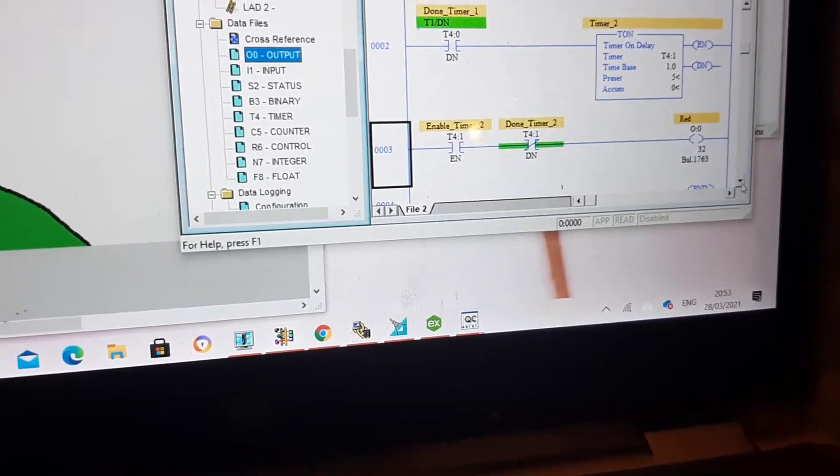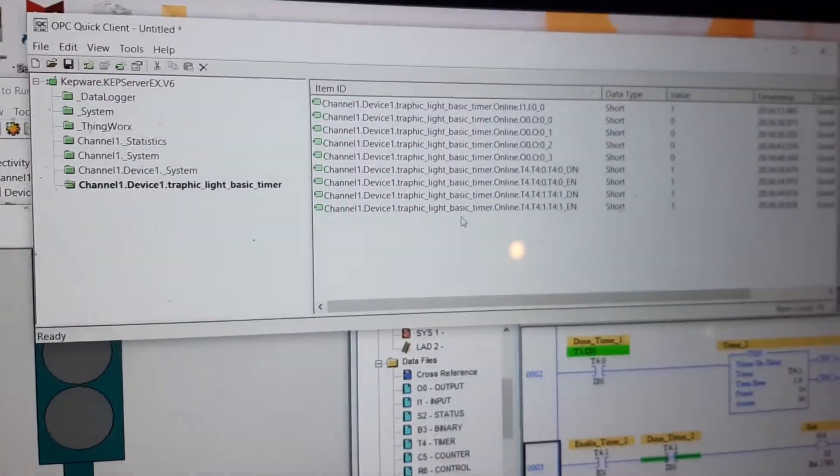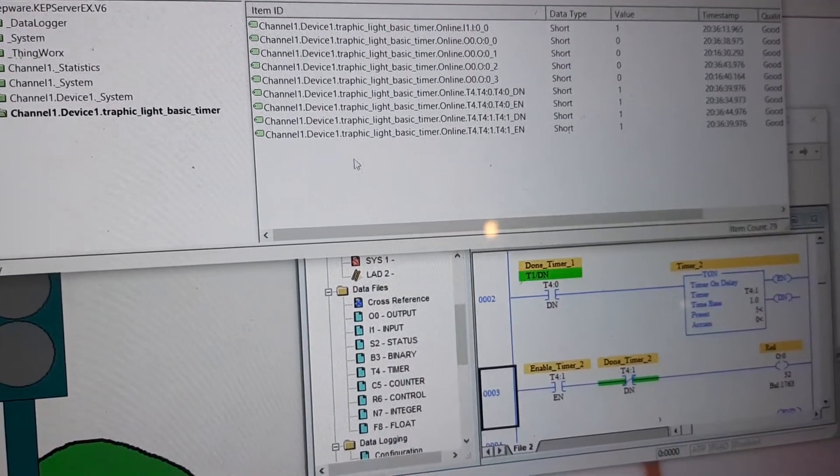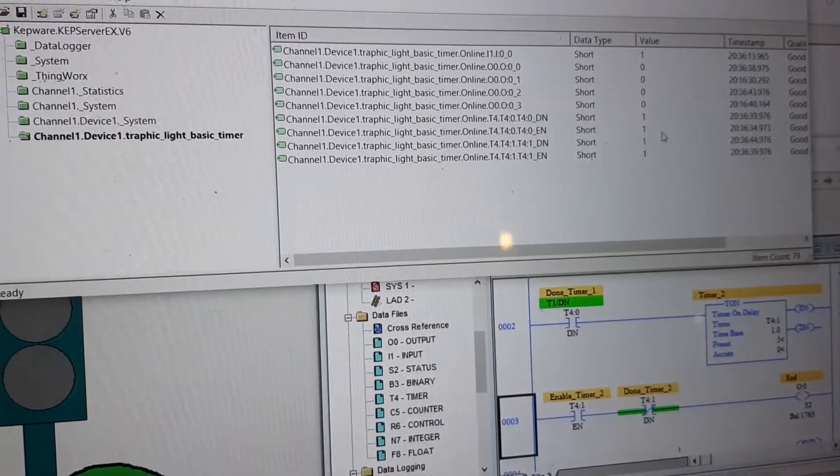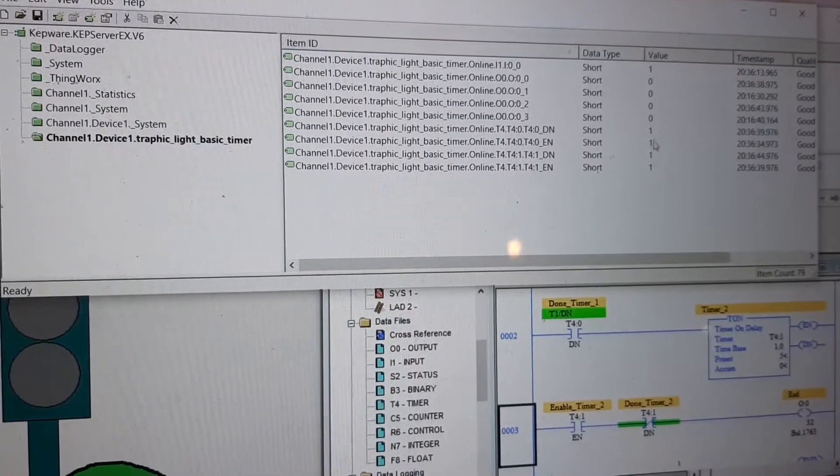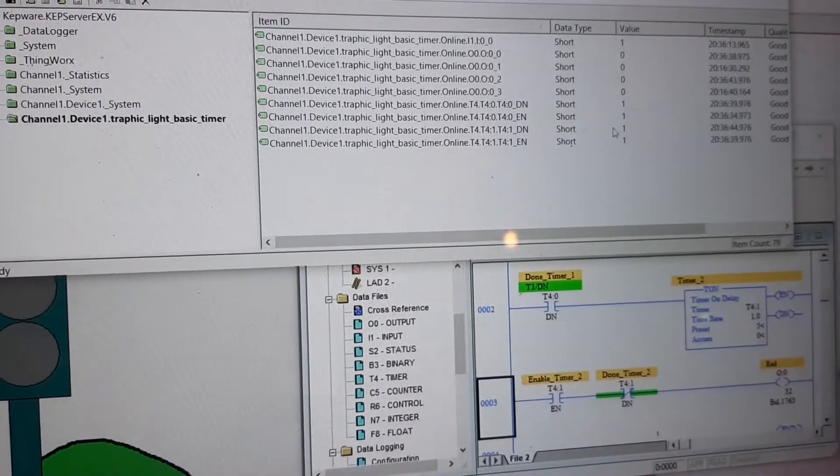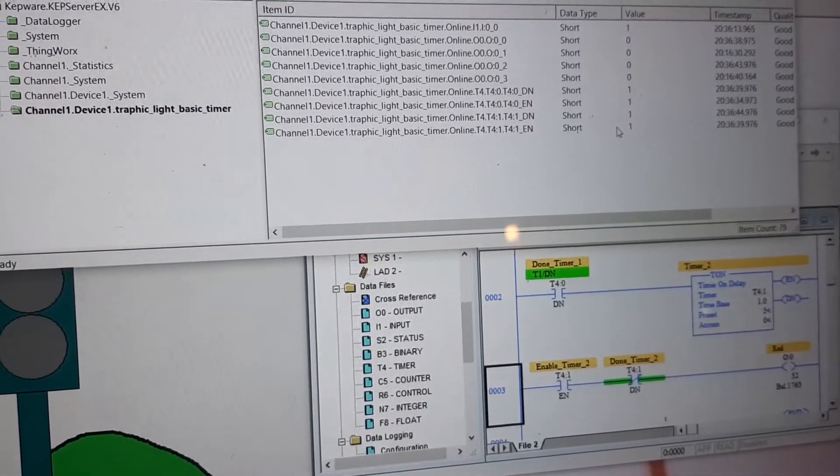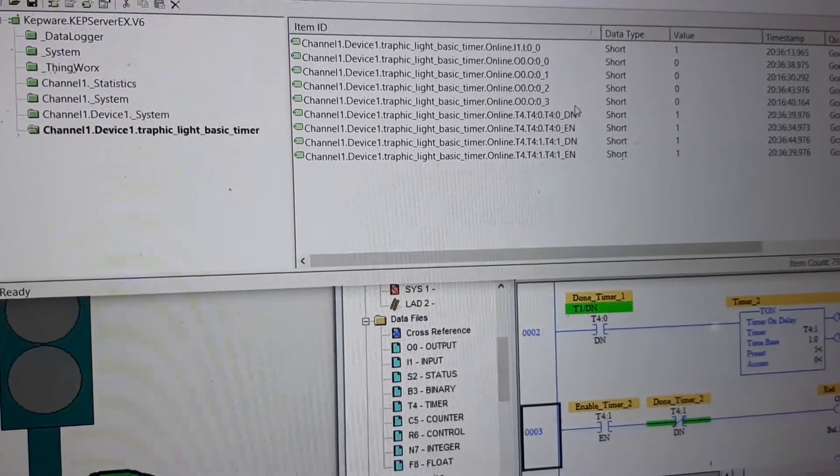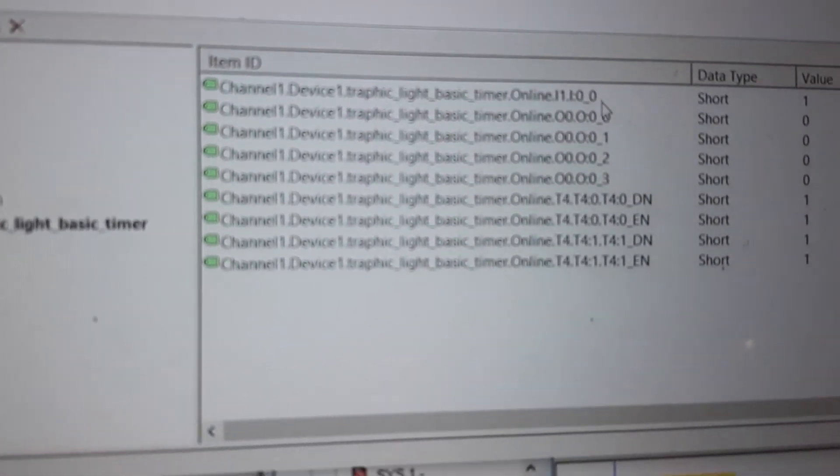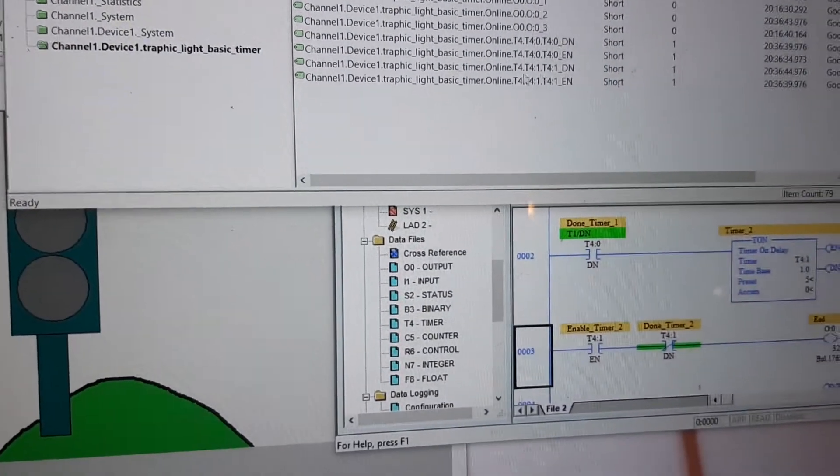And then, what else I want to remind everyone, because I'm receiving many questions and trying to remember all of them. So here, if you see that they are counting up instead of being zero and one, that means that when it comes to addressing you have used the byte address instead of bit address. So be careful of that. So here you can see the way that the addresses are written, take care of that.